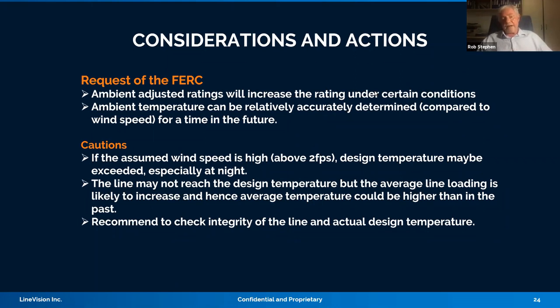A lot of lines that we've found over the years is that if you actually do the temperature and you work out where this conductor is and how far it's sagging, you might find that, gee whiz, we thought we had a 9 or 10 meter clearance, which included perhaps a 0.5 meter buffer that we used. You might find that buffer is no longer there. Or you might find some areas where there's been some variation in the ground levels, which has actually affected the height of the conductor above the ground. So it's always good to do these kinds of checks if you're going to start using some kind of thermal rating increase, either ambient or dynamic rating.